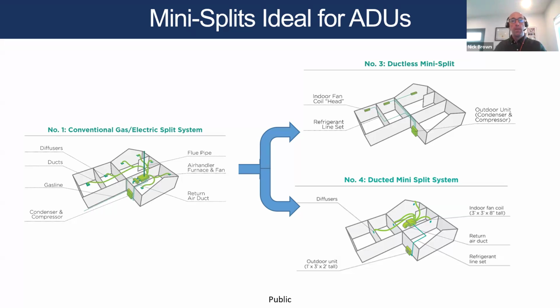So these are super efficient because of what I just told you, their variable speed mini splits are. So a lot of the time, instead of just running until it meets set point at full speed and then stopping and waiting for the building to heat up or cool down enough to be needed again and then going full blast, these are going to ramp down to the same speed as the rate of heat gain or heat loss of the house. And so most of the year, they're able to spend a lot of the time running at low load when they're most efficient, instead of cycling on and off again like the systems we're used to.